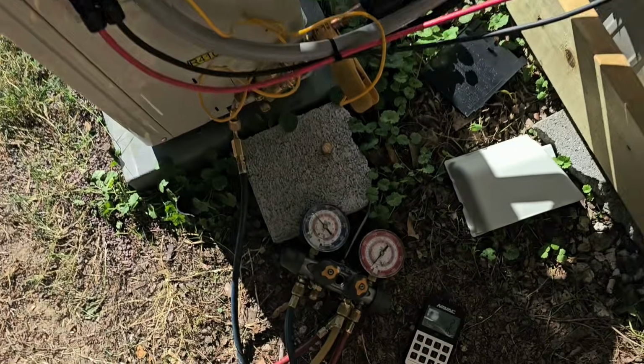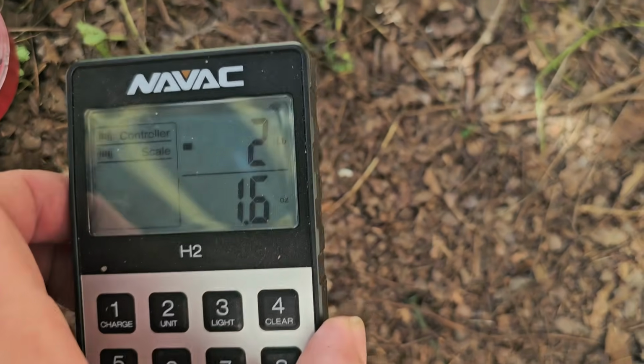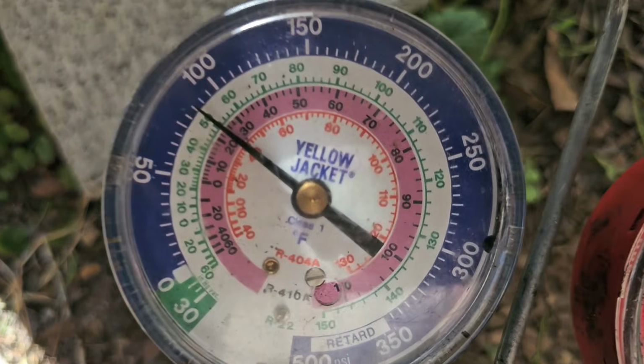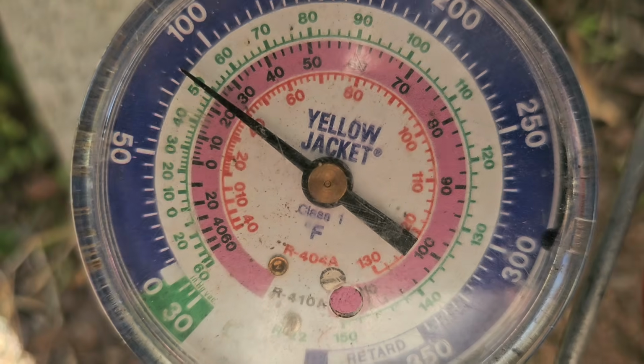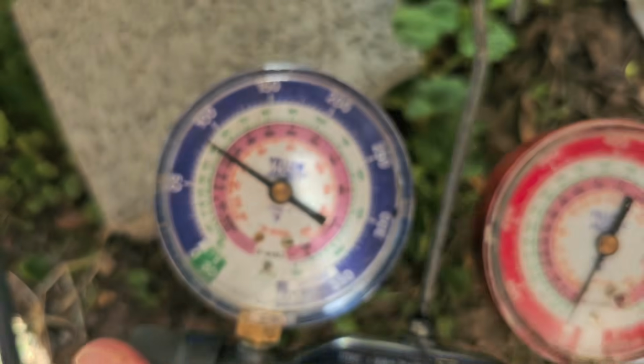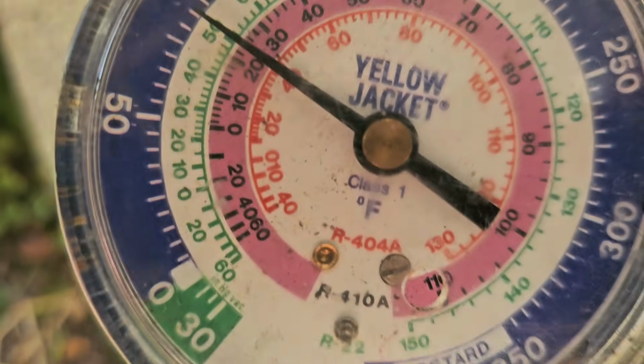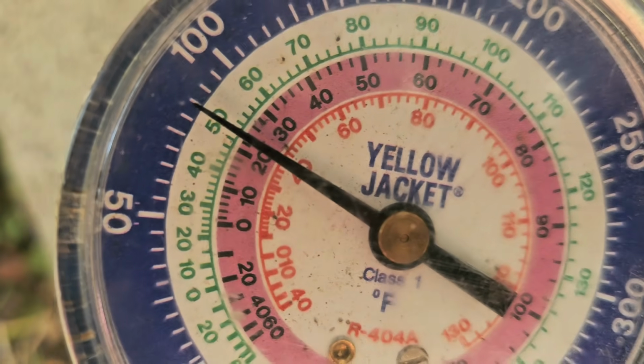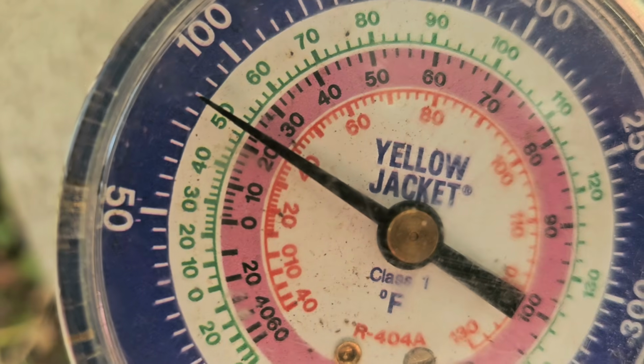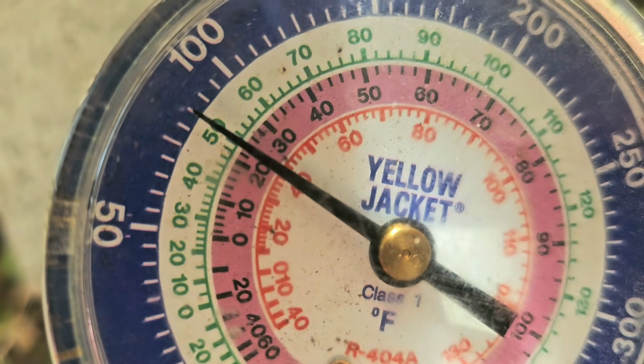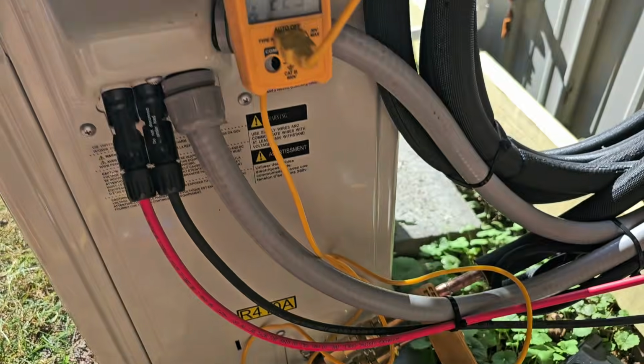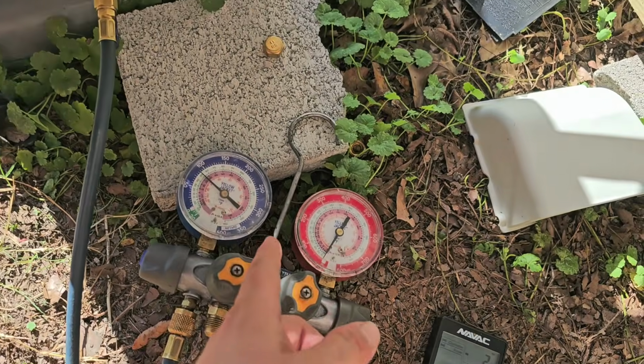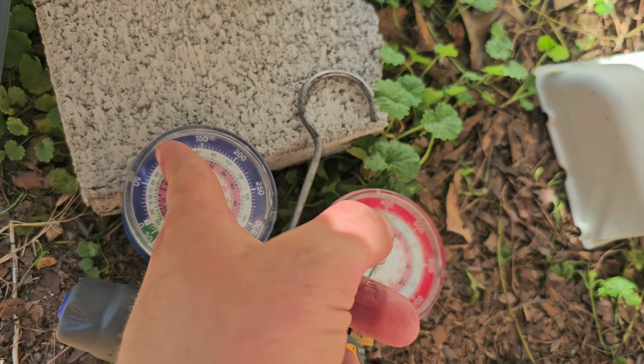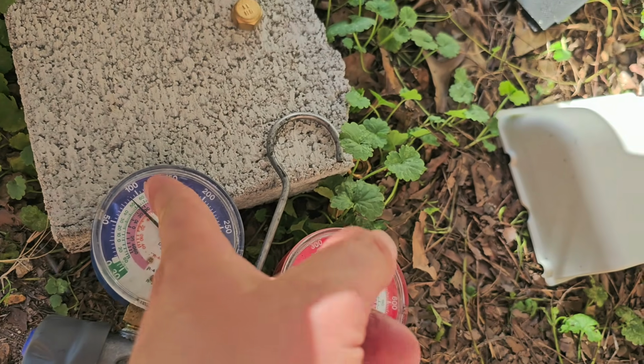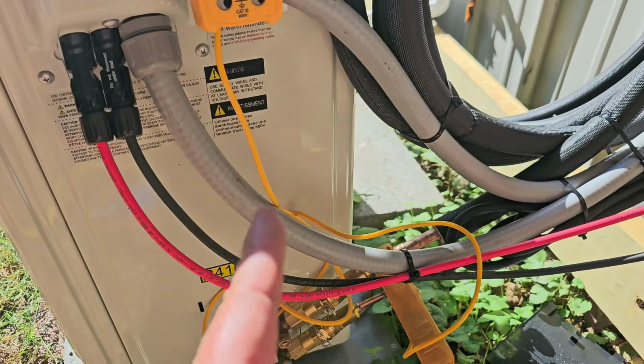Let me show you. So let's see here. We got 2 pounds, 1 ounce of refrigerant. Our low side pressure is, no it's not, it's 75, it's 85. All right, our saturation is that pink line that lines up with R410A, right? Saturation is 23. So 23 is our saturation. Remember that. You get your saturation by looking at the dial that lines up with the pressure, and then where the pink line is, that number is your saturation.